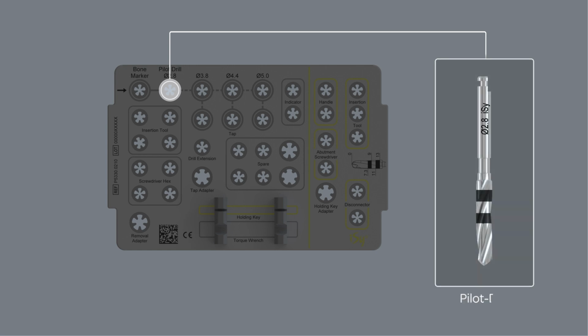The pilot drill, diameter 2.8 mm, determines the depth and axis of the implant site. The depth marks on the drill correspond to the implant lengths 7.3, 9, 11, and 13 mm. The maximum drilling depth is 13 mm.